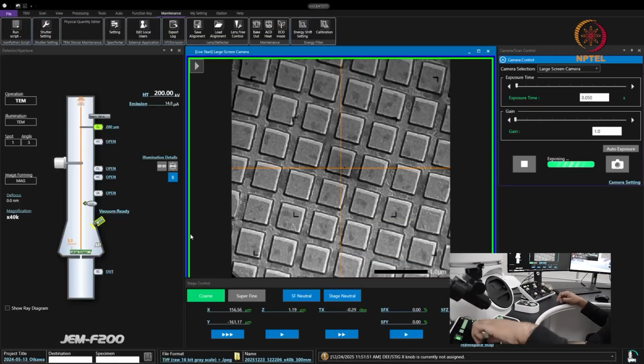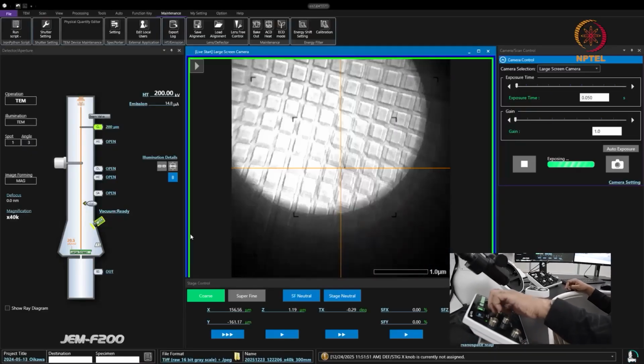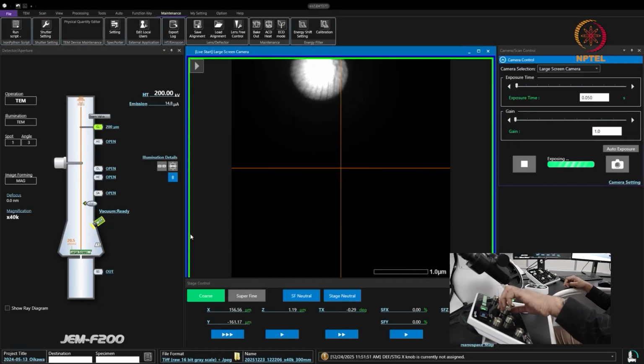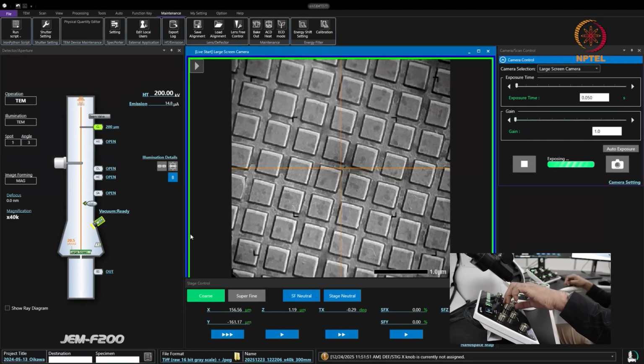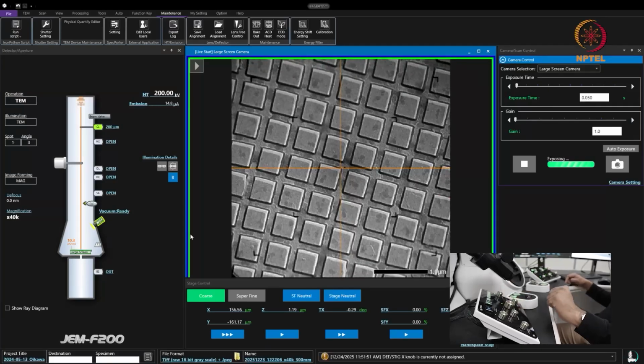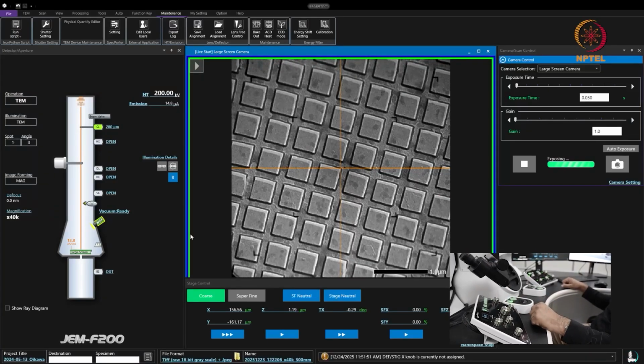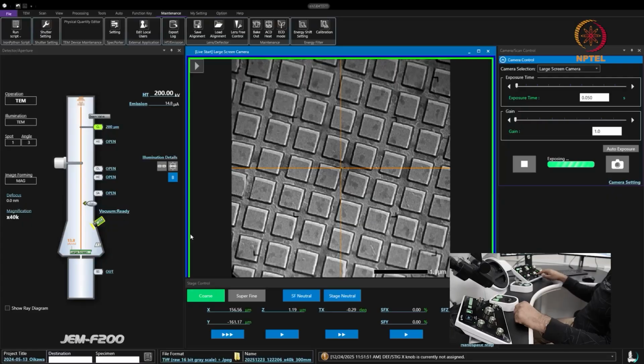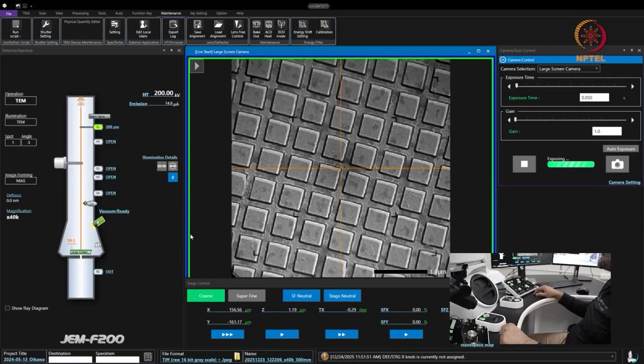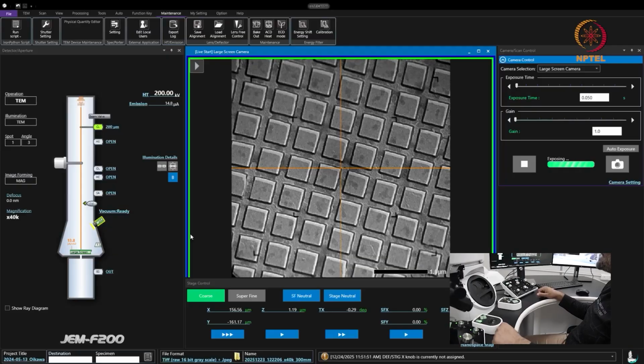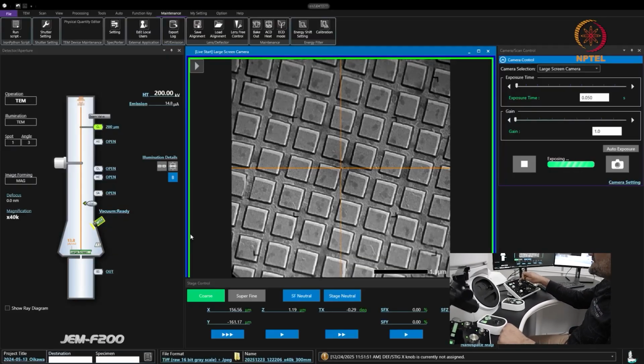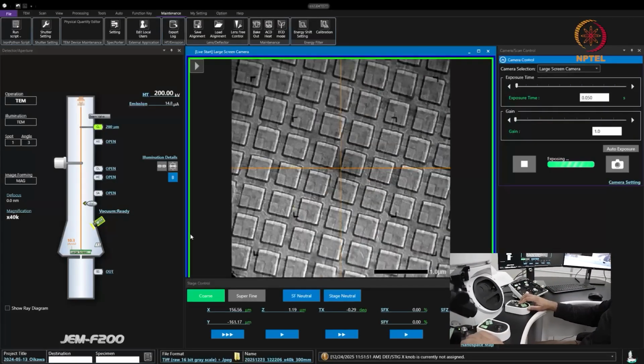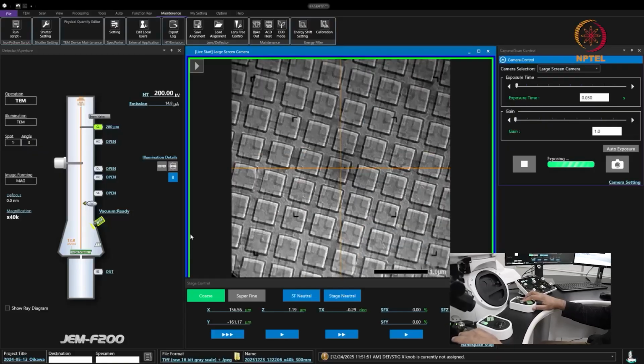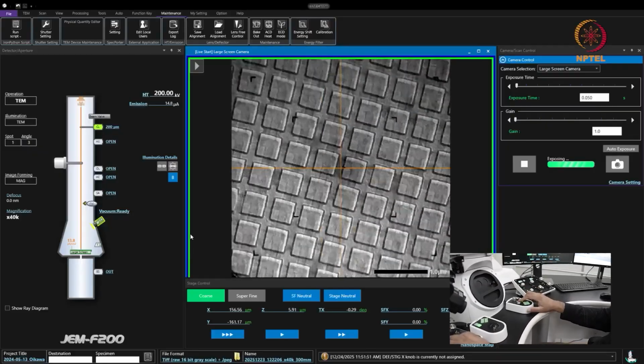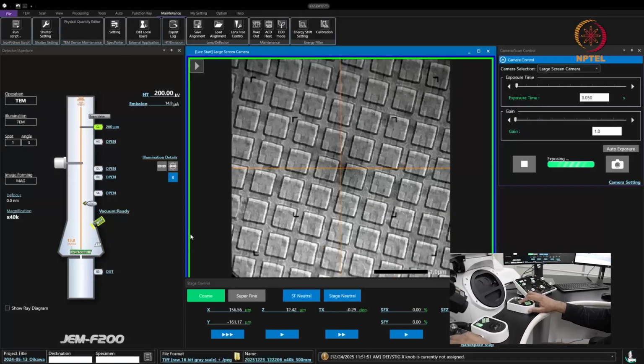Please note that when I change my intensity knob now, your image is actually moving and it is not fixed at one position. This is an indication that your specimen is not at the right height. So I can press standard focus once to ensure that my lens current is set to the eccentric lens current, and now I press the image wobbler button and I can change the height by using the Z knob, or the Z button.